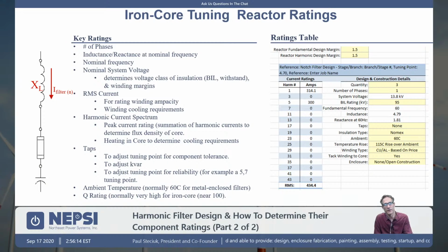And then specify the ambient temperature. Oftentimes we see specifications specifying 40 degrees Celsius because that's a standard temperature. The reality is if it's a metal-enclosed system, the ambient temperature should be set at 60. The outdoor temperature might be 40 Celsius, but the temperature inside the enclosure is realistically 60 C. So specify 60 C on the reactor.